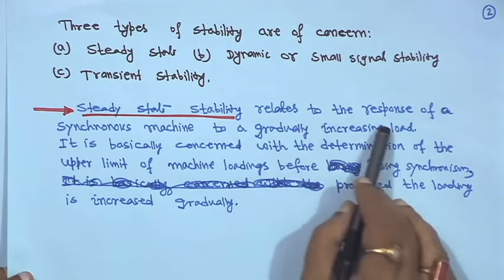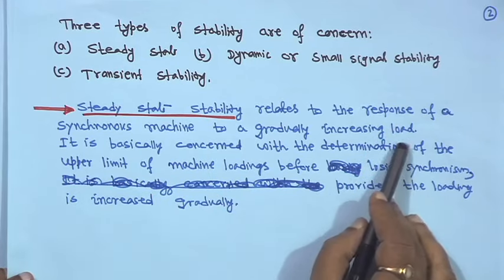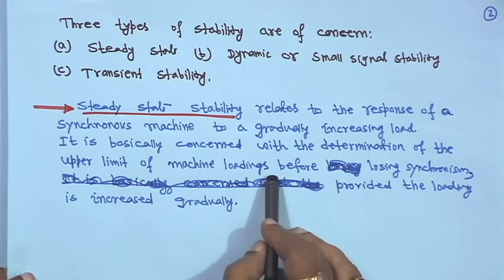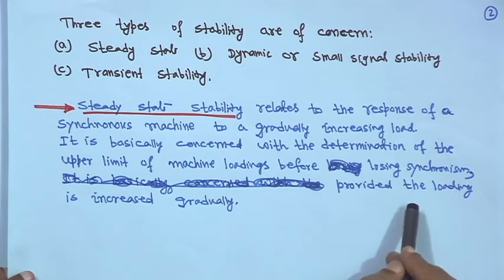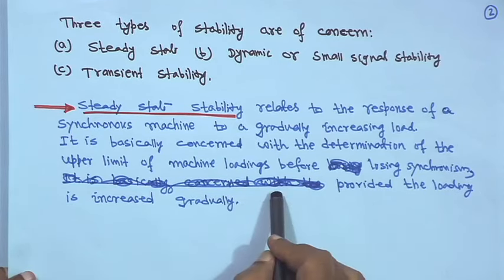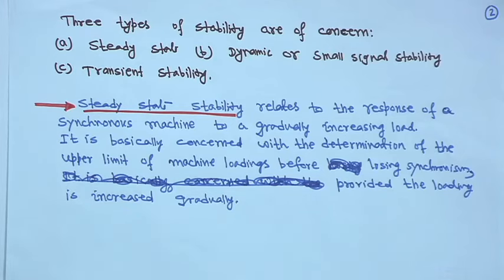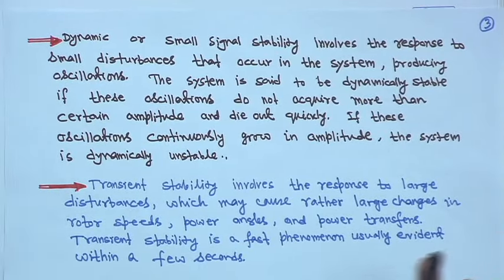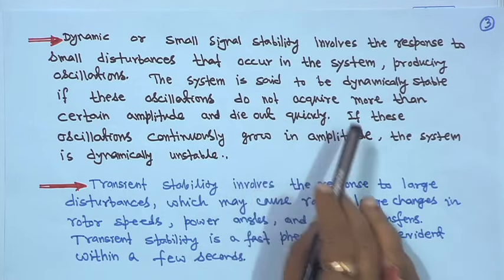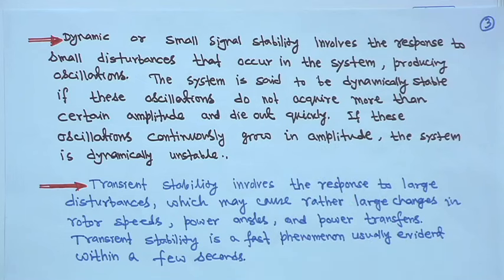Steady state stability is basically concerned with the determination of the upper limit of machine loadings before losing synchronism, provided the loading is increased gradually. The loading will be sustained up to a maximum limit, after which it may fall out of step and lose synchronism. Dynamic or small signal stability involves the response to small disturbances that occur in the system, producing oscillations. The system is said to be dynamically stable if these oscillations do not acquire more than a certain amplitude and die out quickly, but if the oscillations continuously grow in amplitude the system is dynamically unstable.